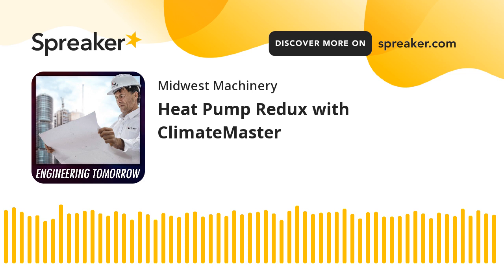Another operation is the occupied mode in winter, since I just discussed winter warm-up, and then occupied mode in the shoulder season, fall and spring. In the winter, and in occupied mode in the fall and the spring, most likely the external portions of your building are going to require heat. These units are going to be running in heat mode, and what's it doing? It is going to be dumping cooler water into the system loop. Now, the interior of the building may not require any heat. In fact, it may require cooling. So these units are actually set and running in cooling mode. So here we are simultaneously heating and cooling our building.